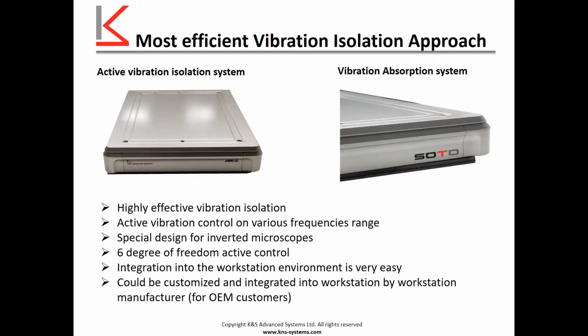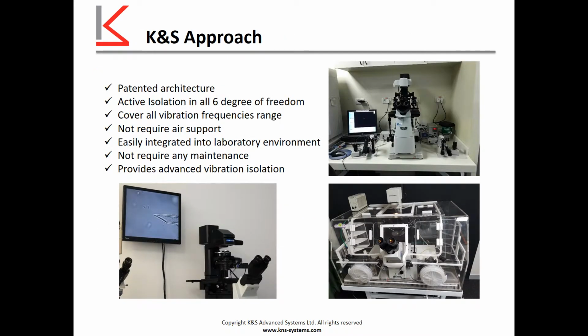What is so special about KNS anti-vibration solutions? There are 2 types of platforms, active and passive. In many cases, passive solution could solve all the vibration problems that persist in the lab. Sometimes, very noisy environment, some special vibration source could require active system. What are the common key benefits of KNS solutions? Highly effective vibration isolation, active vibration control on various frequencies range, special design for inverted microscopes, 6 degrees of freedom active control, easy integration into workstation environment, and finally, it could be customized and integrated into workstation by workstation manufacturer, and this is very important for OEM customers.